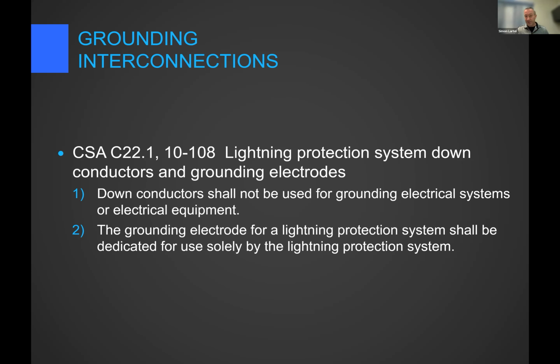Also, in any ground loop situation, you're also going to have an electrical ground grid, and that's going to be separate. That's going to be over near the transformer, or it's going to be underneath the main electrical room or whatever. That's fine. We will connect to that. We'll stay 2 meters away. We'll connect to that, but we're not using that in any sense as our lightning protection ground.